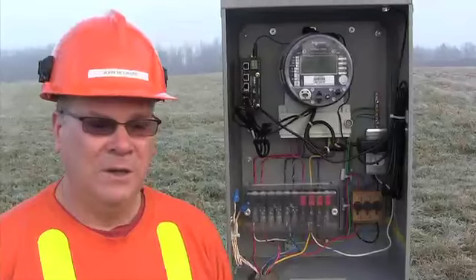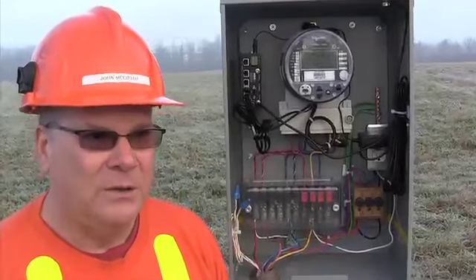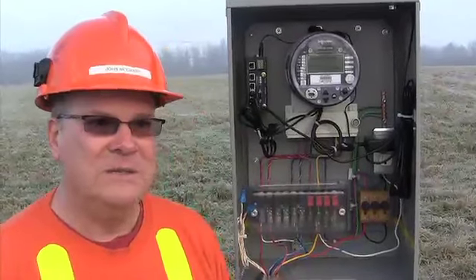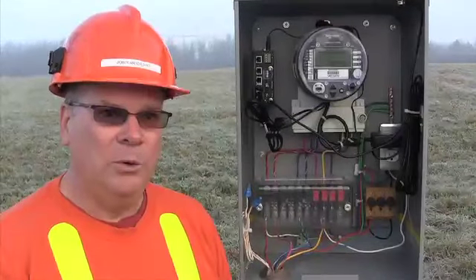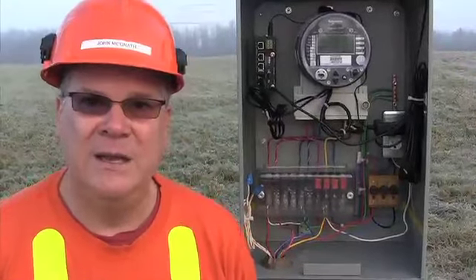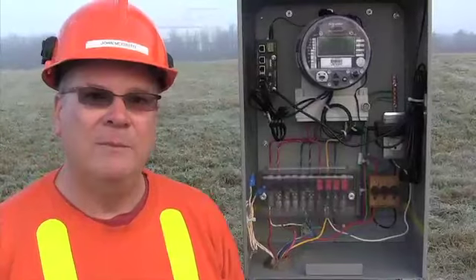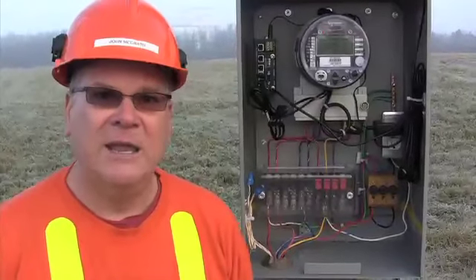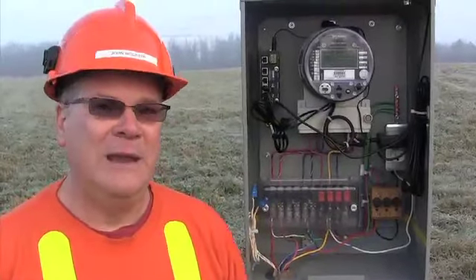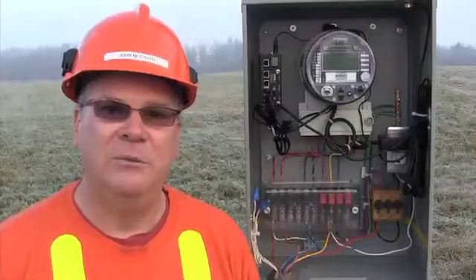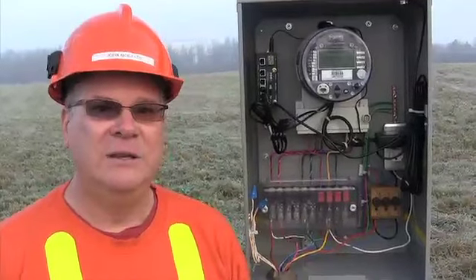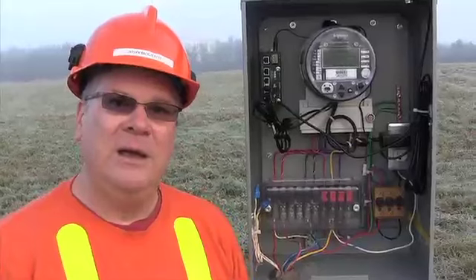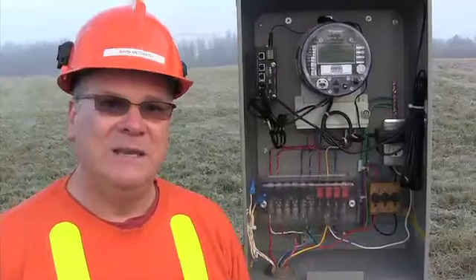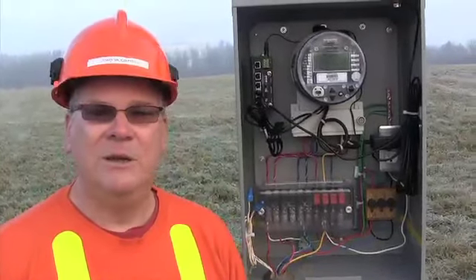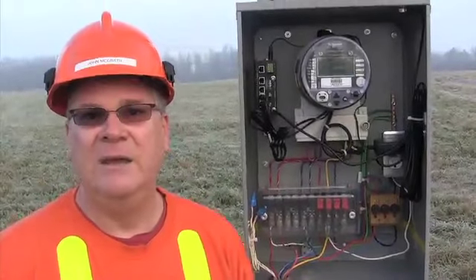With this type of setup, they've told us we can use this primary metering, the Ion 8600A, and they're there if we're out in the field doing work. They can actually look inside the meter, see what we're doing, and confirm things look good, and we also do a comparison with an end-to-end test.